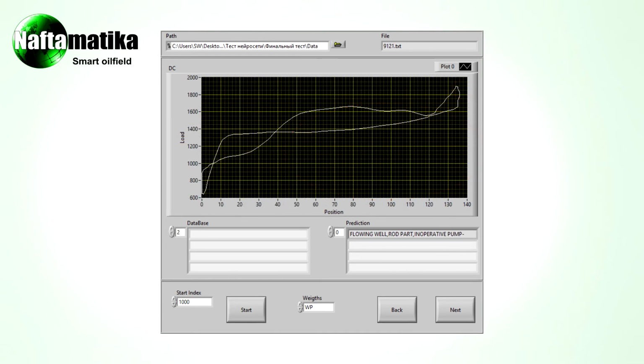If the previous card was simply not optimal, then this one is already an emergency and requires an immediate stop and urgent repair. Breaking of rods and gushing of the well, perhaps you can't imagine worse. But by timely stopping of the well, it is possible to reduce downtime by the time of the repair.